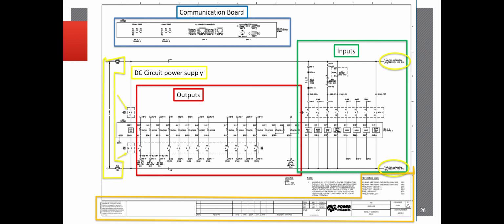The green box is all the relay inputs. Those are the signals that you're going to be receiving from either other relays or even the high voltage equipment itself. You can see on the left of this green box there's a 52.1A contact. That is a breaker contact that indicates whether the breaker is open or closed, and that's what we'll be utilizing to monitor the breaker that's in the relay circuit. As well as general notes. Usually it's just stuff that you want to make sure people look out for if they're doing any testing or if they're going to be operating any of these pieces of equipment.